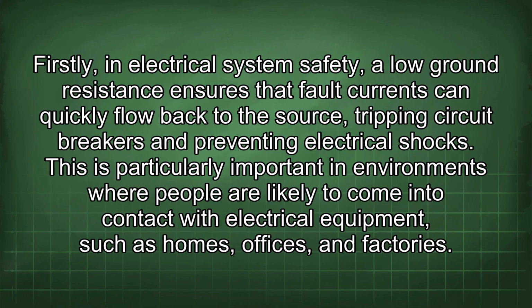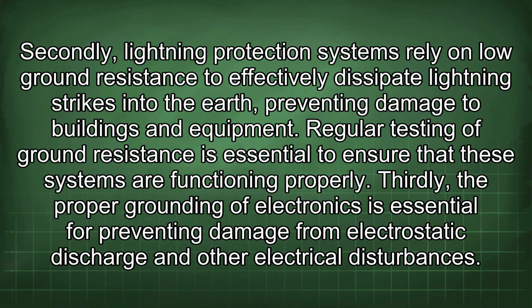Firstly, in electrical system safety, a low ground resistance ensures that fault currents can quickly flow back to the source, tripping circuit breakers and preventing electrical shocks. This is particularly important in environments where people are likely to come into contact with electrical equipment, such as homes, offices, and factories. Secondly, lightning protection systems rely on low ground resistance to effectively dissipate lightning strikes into the earth, preventing damage to buildings and equipment.